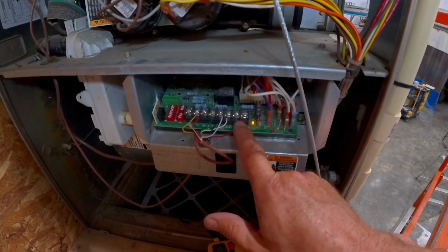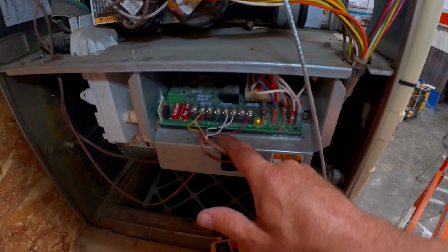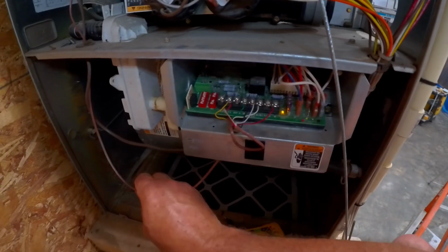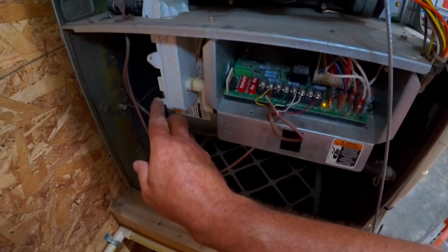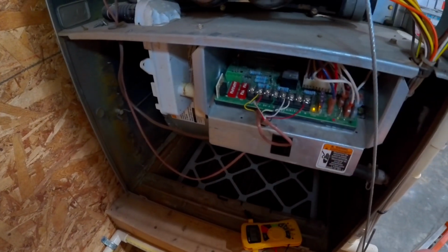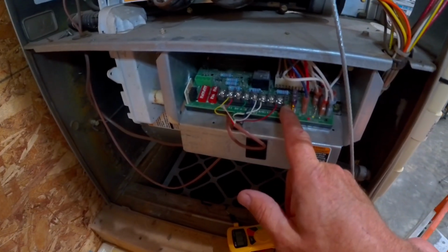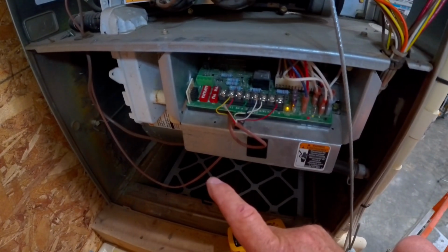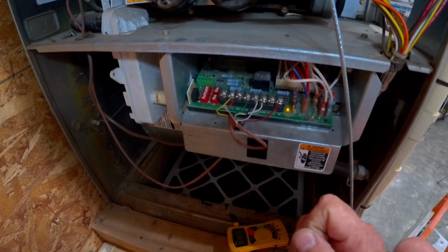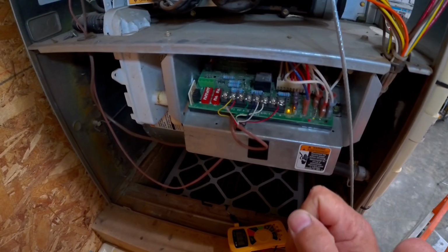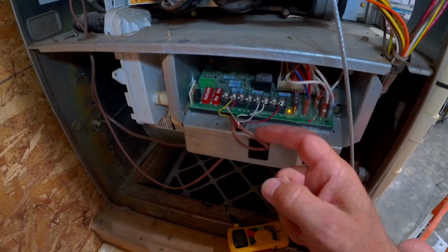And that is sending 24 volts to our thermostat through this thermostat wire right here. So this goes over to the house and onto the wall into the thermostat. So 24 volts going out of the R to the thermostat. And then depending on what your thermostat is telling the furnace to do, it sends power back down certain wires.